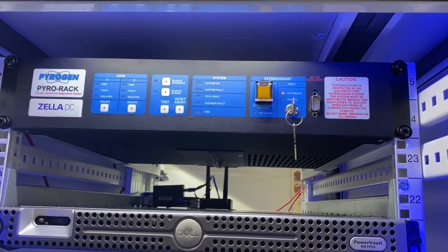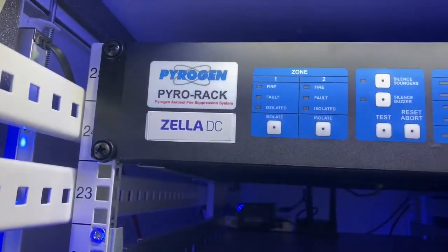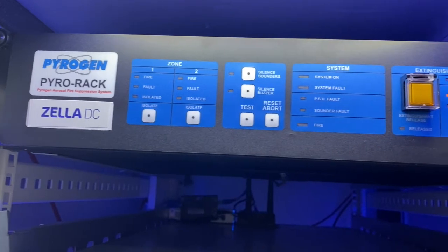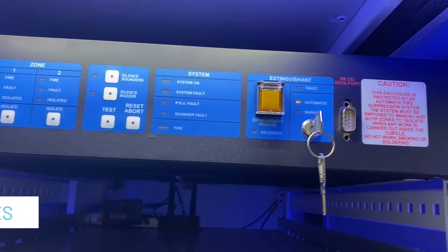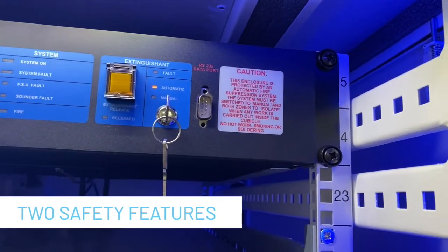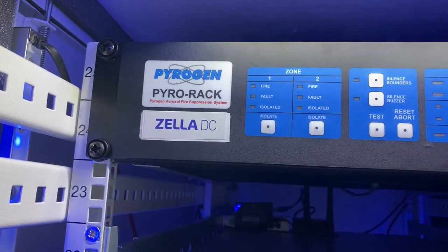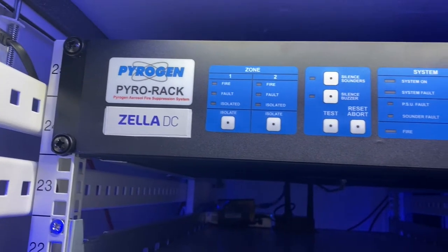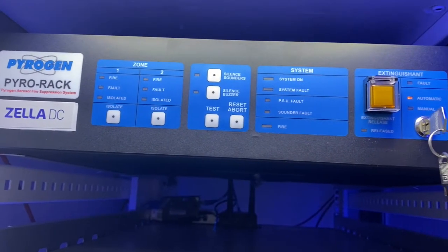A key feature of the Pyro-Rack extinguishing canister is that it is not solely reliant on the automatic detection system for operation. It has two inbuilt fail-to-safety redundancy features: its own dedicated heat sensing cord that will operate at 175 degrees C or if it is in contact with naked flame, and if this heat sensing cord is not present, the extinguishing canister will self-operate when it reaches 500 degrees C.